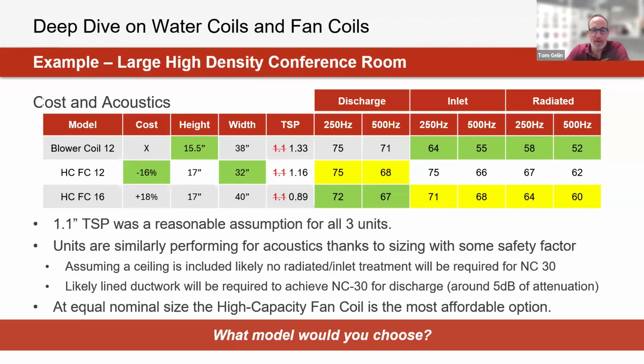This is what I'll share, and what we don't have time for today: when you use Price's software to pick fan coils, you don't have to go through the selection of blower coil 12, high capacity fan coil 12, and so on. It's all put together. You can see all the data at the same time, which is really nice. So this side by side that Braden put together is not exactly at your fingertips like this, but it's pretty close. You can see multiple fan coils at the same time with sound data, with the pressure drop, with the coil performance, with the number of circuits, with the number of rows, et cetera.